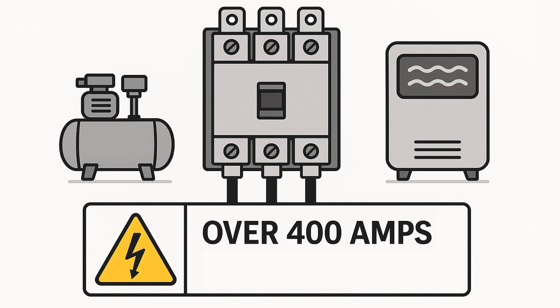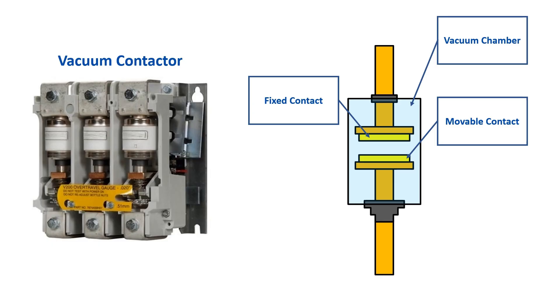One final note about contactors. When you're dealing with currents over 400 amps, it's recommended to use vacuum contactors. At these high current levels, there's a serious risk of arc flash during switching. Vacuum contactors solve this by sealing the arc inside a vacuum chamber. With no air or oxygen, the arc is extinguished almost instantly. That makes them not only safer but also longer-lasting.